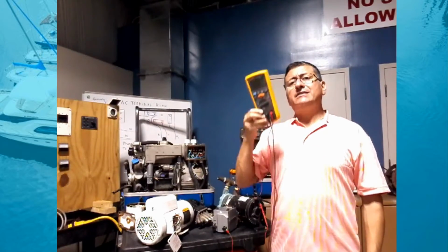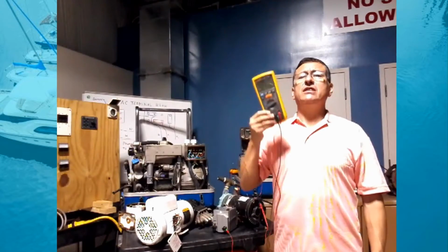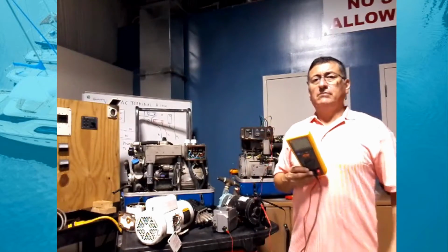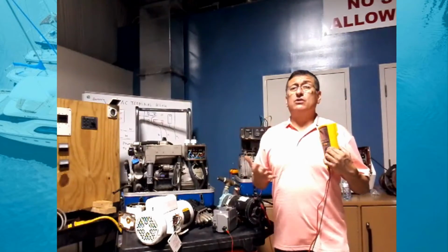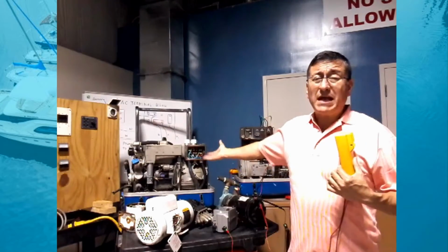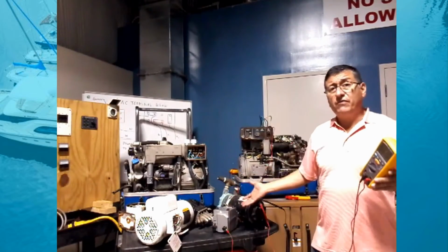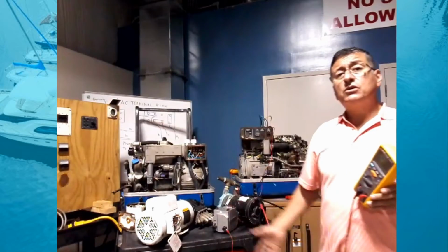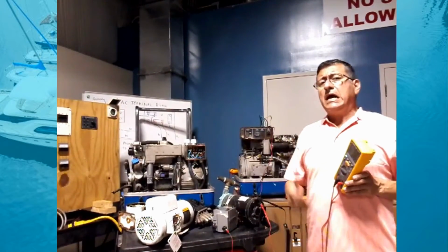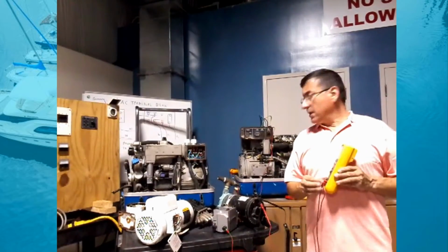The megohmmeter is an equipment used to check the quality of the insulation in the winding of any motor or generator or equipment. I use it to check the motor of bow thrusters, the starter motors, alternators, and of course, the back end of generators. Okay, I have a couple of AC motors, and also the back end of the generator, and I am going to explain in a simple way the procedure to use the megohmmeter.